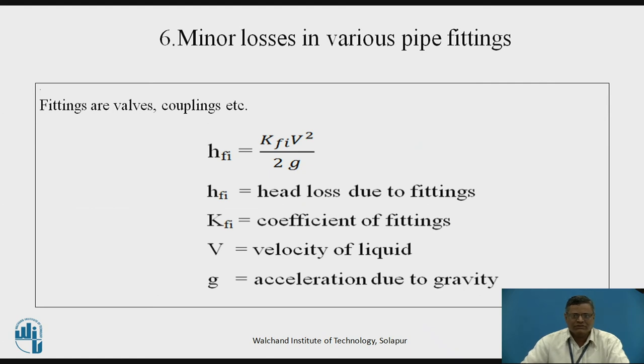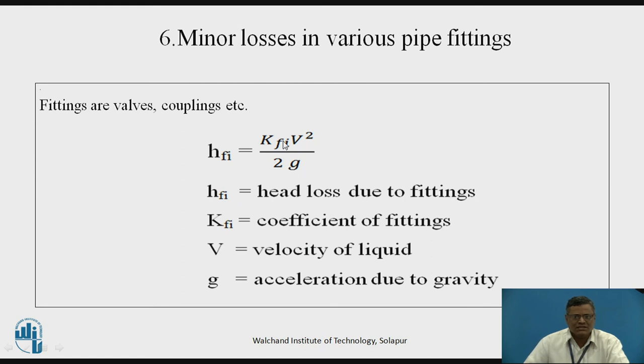Minor loss in various pipe fittings. Different types of pipe fittings are generally used, such as flow control valves, shut-off valves, and different types of couplings to join two pipes. The head loss in pipe fittings, HFI, is given by the formula: KFI × V²/2g, where KFI is the coefficient of the fitting.